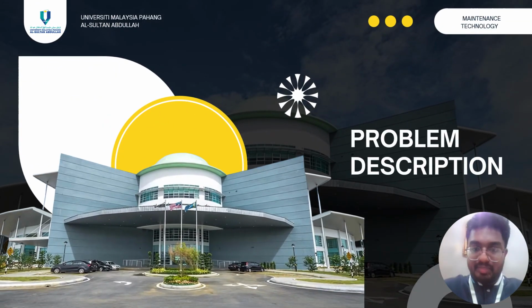Let's start with the problem description. The equipment in question is the cooling water pump motor located at the SPD plant process area. The failure event was detected during a routine inspection round. The operator reported excessive vibration and loud abnormal noises coming from the motor's non-drive end bearing. This is a critical issue because if the pump fails, it carries a high risk of cooling system breakdown.